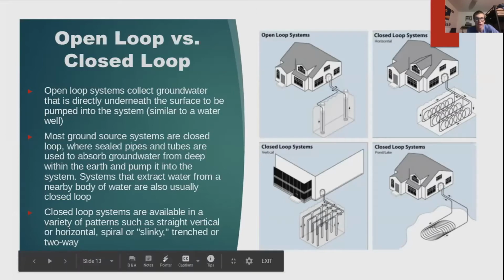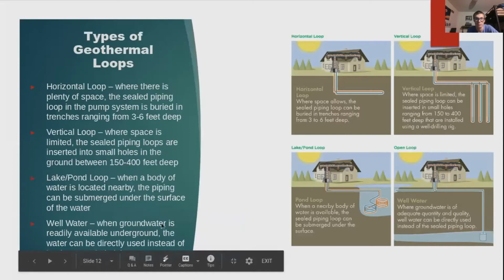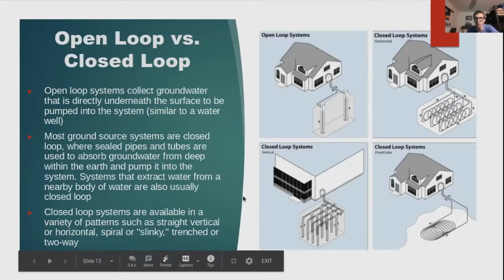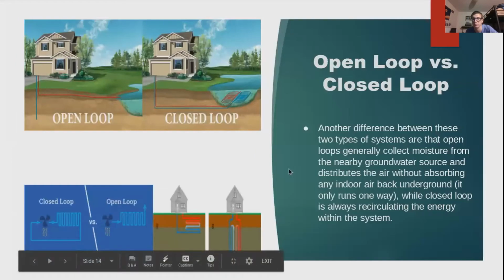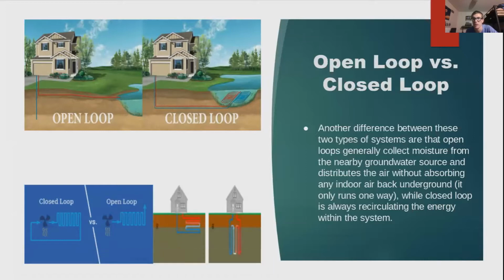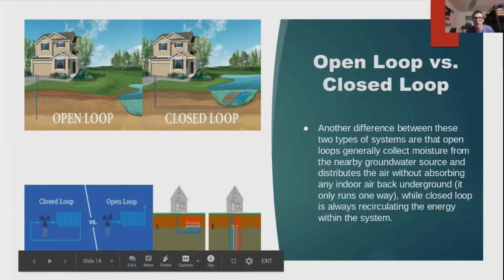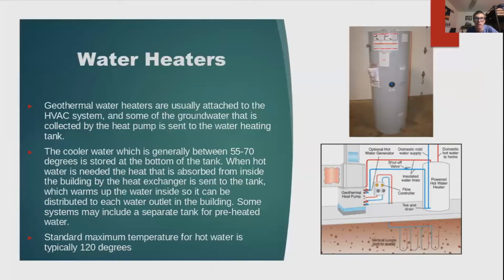The closed loop systems are available in a variety of patterns, including just regular vertical or horizontal, which we see here. And lots of other cool patterns too, like the spiral or slinky, or just a deep trenched or a two-way. Another major difference that I found between these two is that open loops usually run only one way. It simply collects the energy from underground and sends it throughout the building, but it doesn't necessarily collect any indoor conditions and recirculate it back to the ground, whereas closed loop does recirculate, much like a conventional system.